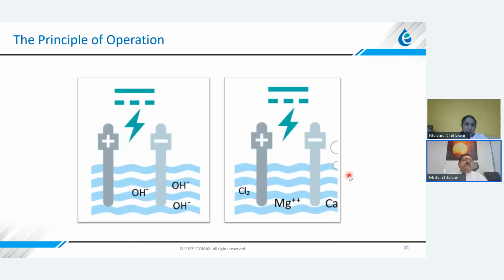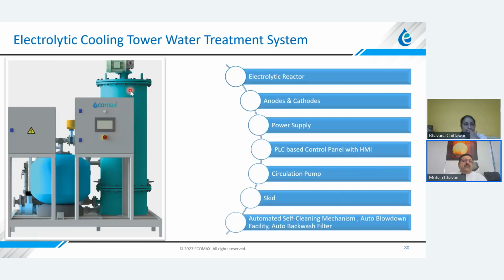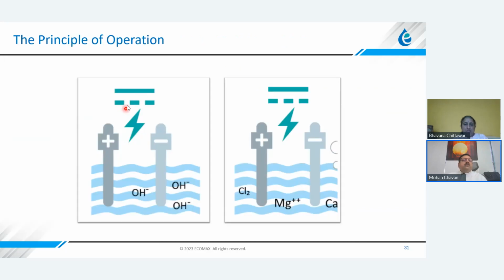Let's look at the principle of operation of this technology. First and foremost, here we have anodes and cathode in this reactor, green chamber. Once we give electricity or power supply to anode and cathode, we generate OH minus ions. The moment we do this, we will have a separation of calcium, magnesium in the water, and they will try to migrate to the cathode, which is the negative electrode. And simultaneously we generate chlorine gas from the chlorides in the water at the anode.